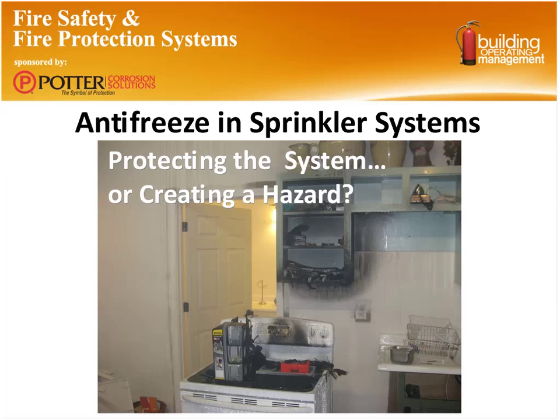Our first topic is antifreeze and sprinkler systems. Protecting the system or creating a hazard? Some people do not even understand that they do have antifreeze sprinkler protection in their facility, but it is more common than you think. Freeze-protected sprinklers would typically be in docks and some of the areas that could see cold, but are not quite large enough that they would demand what we call a dry sprinkler or pre-action type sprinkler system. So it's a more cost-effective way to freeze protect.